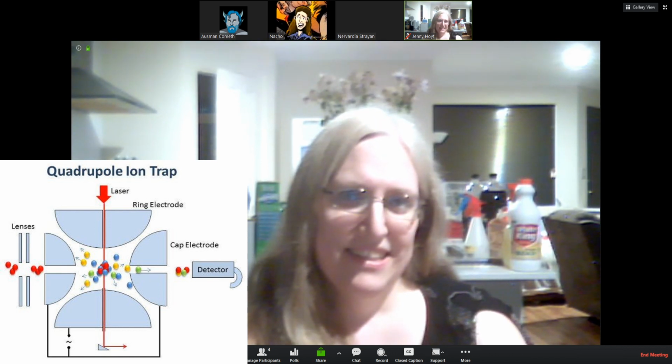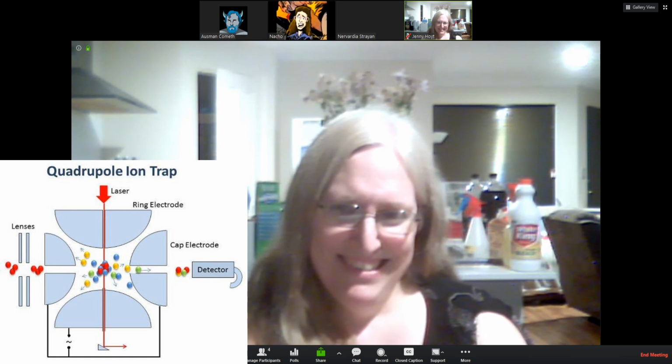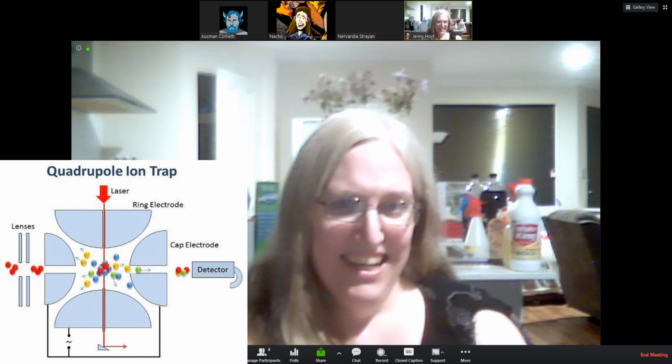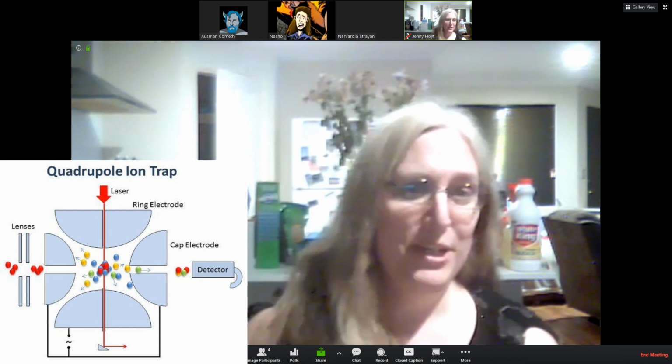So it's actually more sensitive. It's about 10 to 100-fold more sensitive than the other quadrupole analyzer. So it's a trap that folds in on itself, and then you've got ions that are getting excited, and then it becomes more sensitive.